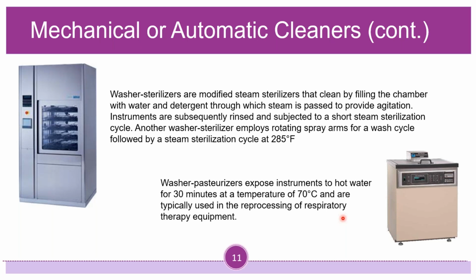You can take a guess. Krista, yes, to not damage plastics. Perfect. So it's less than the temperature that typically damages plastics, right? So very good. So 70 degrees Celsius is about 158 degrees Fahrenheit, and some plastics have a melting point as low as 165 degrees Fahrenheit. So yes, absolutely.